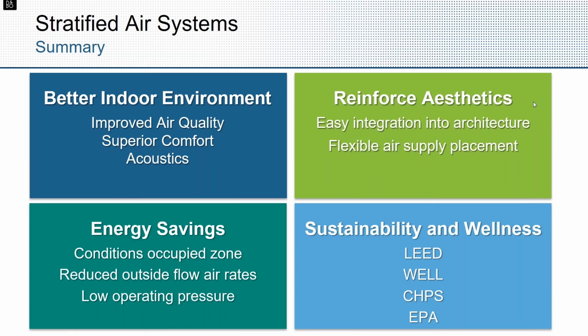There have been a couple of methods for conditioning schools in the area. Some still use a ventilation-only approach, which might be less than half a CFM per square foot. A lot of schools are moving to cooling and ventilation. Without getting too specific, even with a 65-degree supply air temperature, displacement doesn't need double the CFM—what might not be obvious is that because you're conditioning just the occupied zone, you end up with about the same CFM per square foot needed, or even less, despite that elevated supply temperature.